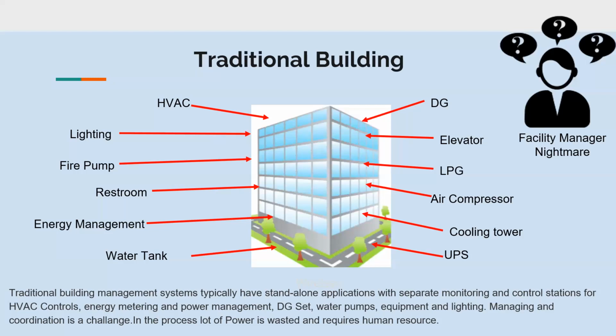Similarly, you have energy meter mapping where energy meter data is noted every 12 hours or 24 hours, but that doesn't give you any idea regarding your consumption pattern. Then you have your water management, again one of the neglected resources. There is no proper monitoring of the consumption parameters, and a lot of water gets wasted. Then it comes to your fire pump. The jockey pump runs frequently, and hydrant pressure is not being maintained. Fire drills are not being conducted properly, and the water in the fire water tank is being used for other purposes such as gardening, cleaning, etc.